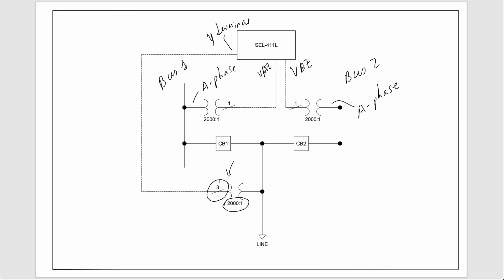Now in this case, for the bus side PTs, I'm assuming that we have Y connected PTs, and that's of course again because we're using the single phase A phase to ground voltage for both sides. So all three PTs are going to be Y connected.